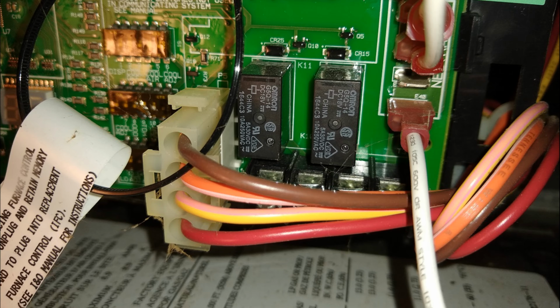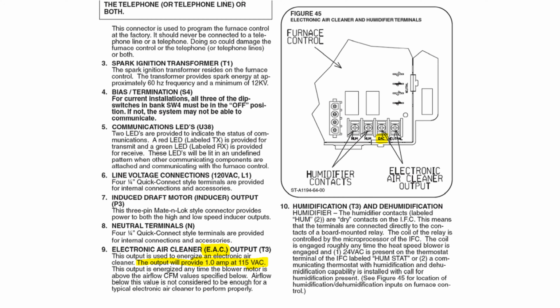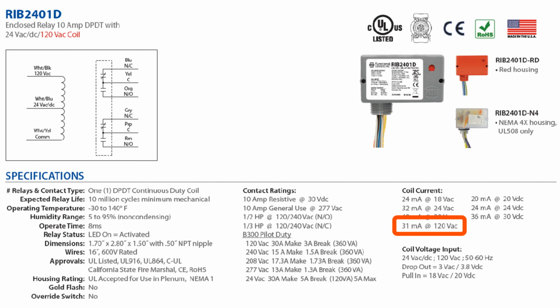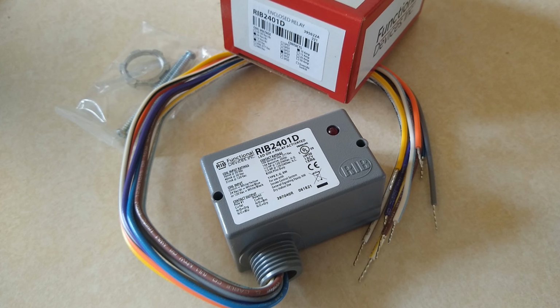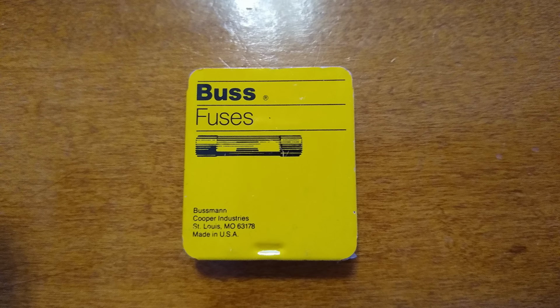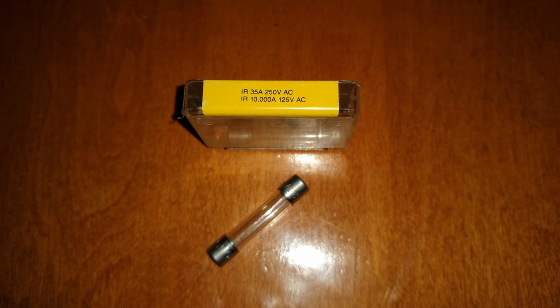warranty. I don't know. The EAC output is limited to 1 amp at 120 volts. The relay coil I use draws 31 milliamps. That's 0.031 of an amp, so it barely registers. There's no risk of overloading that output and damaging the expensive control board by using this relay. However, I'm actually updating it with a fuse to protect it from the highly unlikely event of a downstream short circuit.